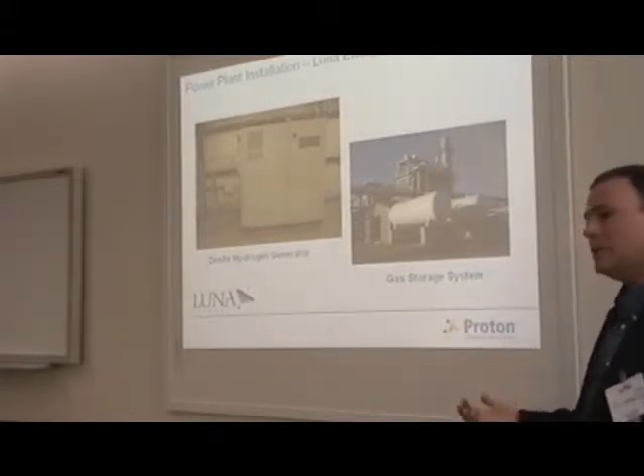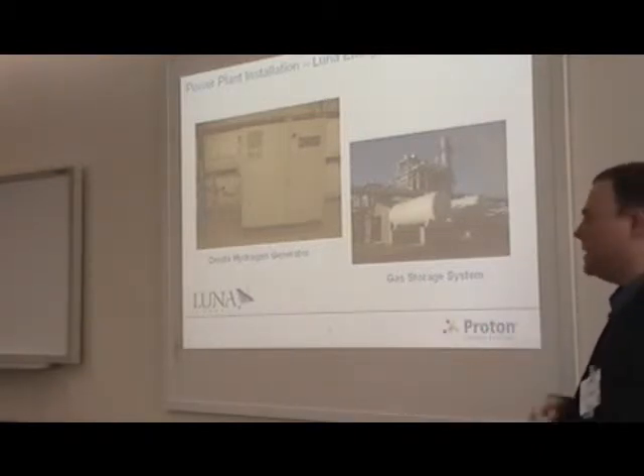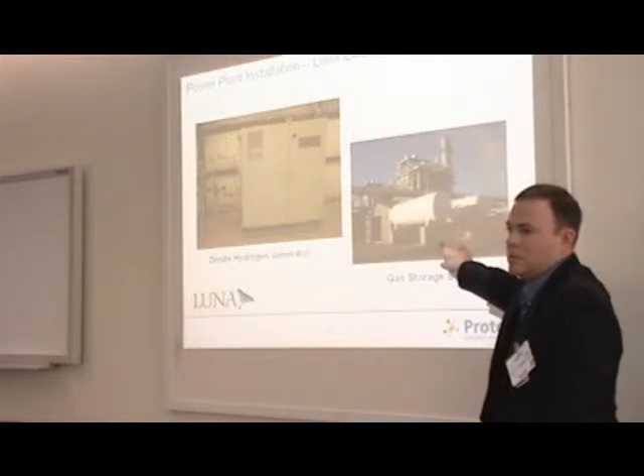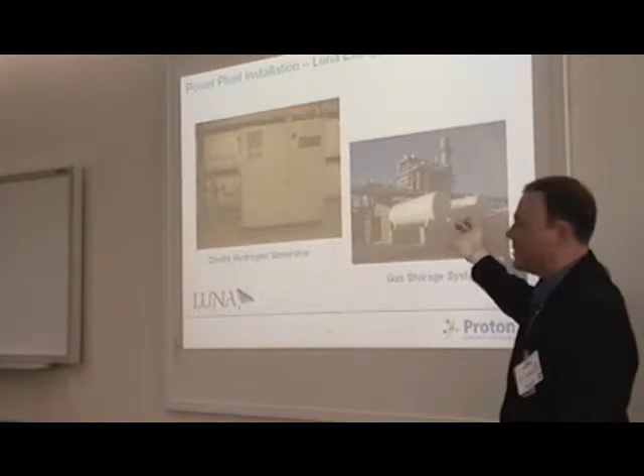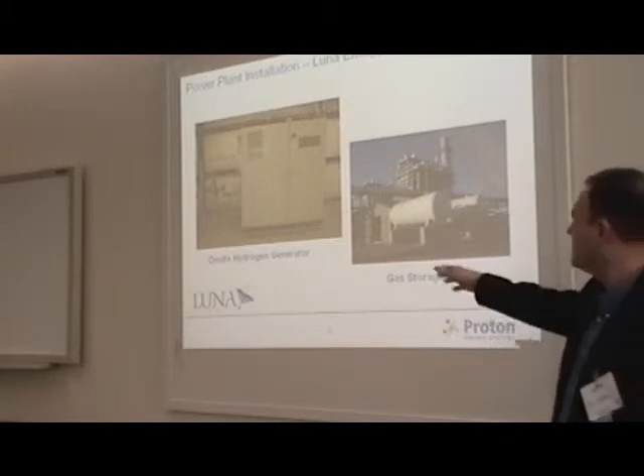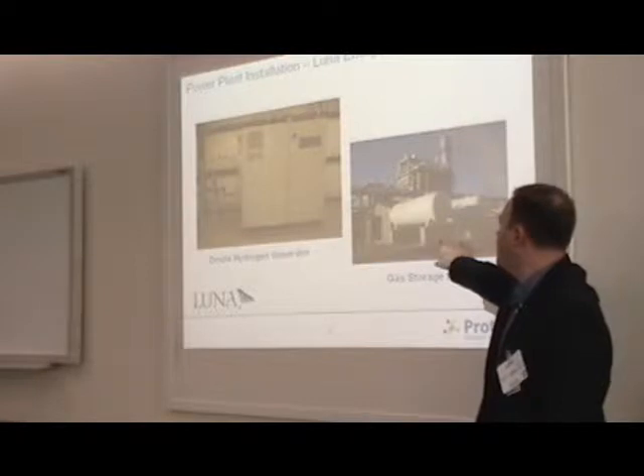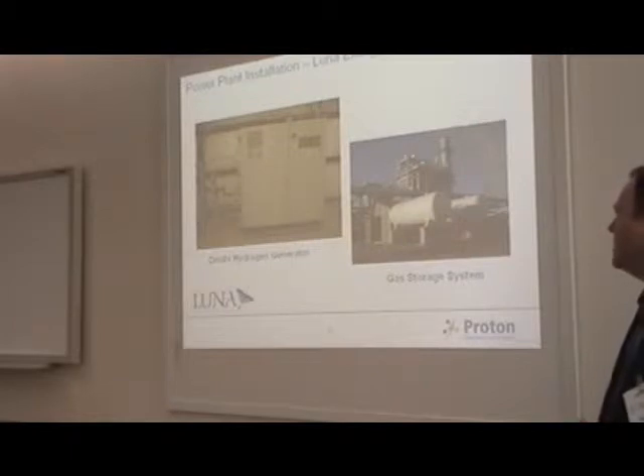When they go into an outage situation, they would shut off the hydrogen generator, do their outage work, whatever it might be. They need to regas the generator. They pull those larger volumes of hydrogen from their stored hydrogen that's been valved off all this time, just sitting, not connected into the plant. Fill their generators back up, start up the hydrogen generator, the daily makeup goes to the plant. The excess generation refills these back to 200 psi or 400 psi. They get valved off again and wait till next year when they go through another outage. It's a very simple, straightforward solution and allows them to be completely independent from hydrogen deliveries.